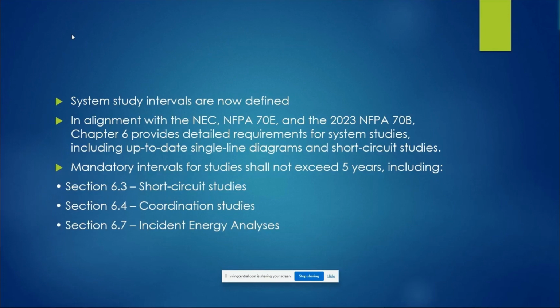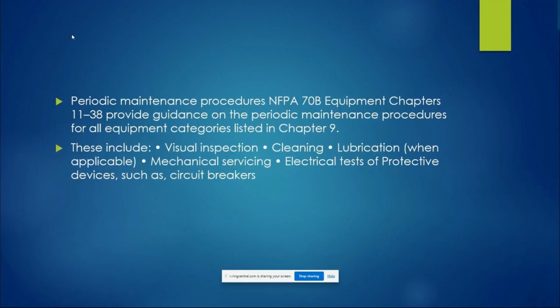Short circuit studies, coordination studies, and incident energy analyses are all three things that we offer as part of our arc flash studies. Our arc flash studies run parallel to the NFPA 70B program. So anytime you need mitigation, which is a nice fancy way of saying lowering the hazards, that's part of a coordination study. Short circuit studies we do in coordination with your utility company to try and find a way to reduce the short circuit analysis of your main transformers coming into your facility. And then, of course, incident energy analysis gives you the calories per square centimeter that you're exposing your employees to when they're opening and working on live equipment.